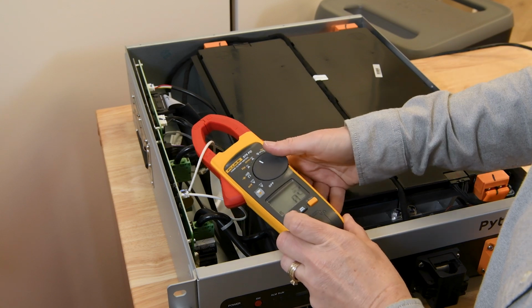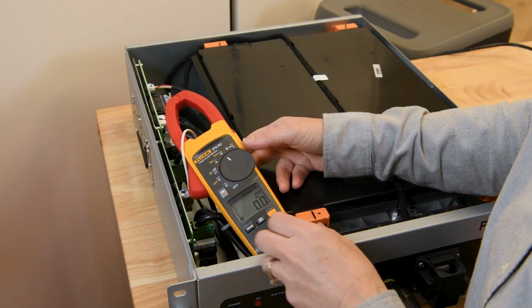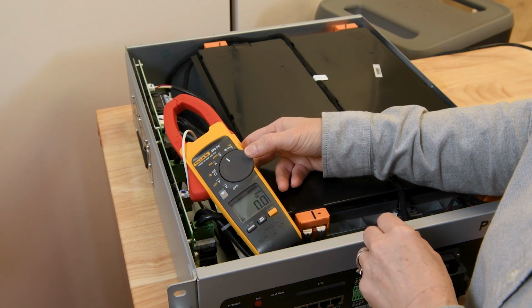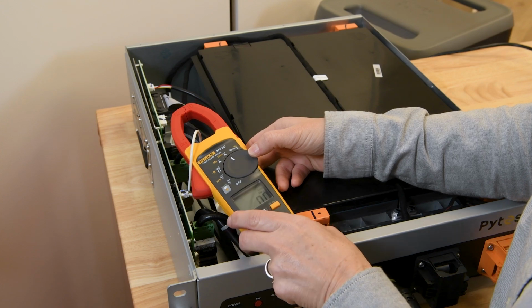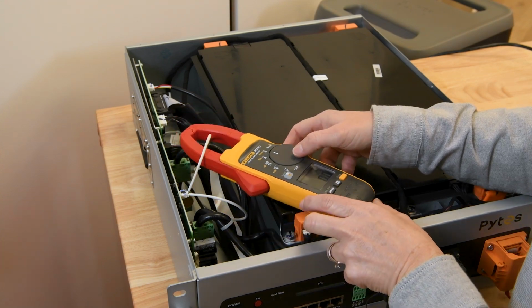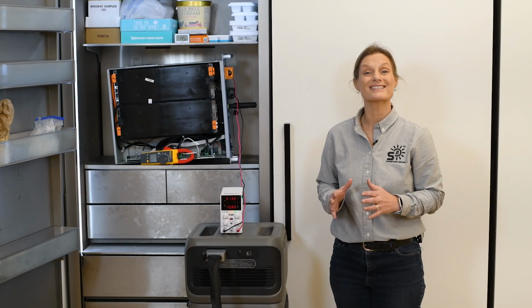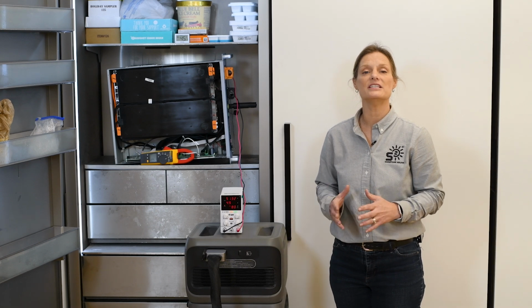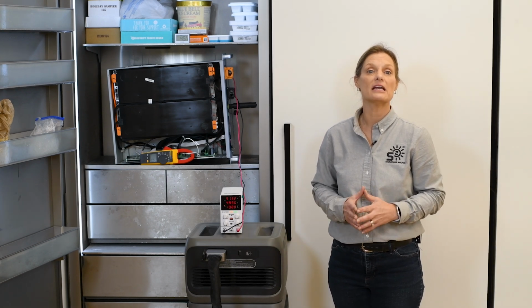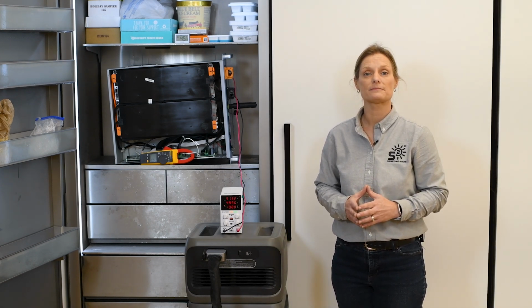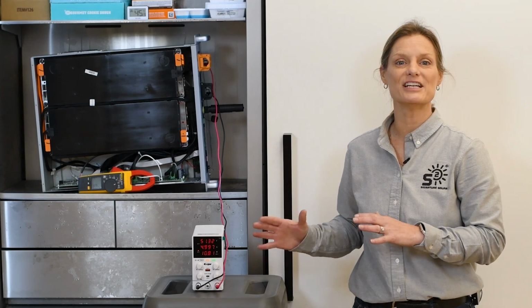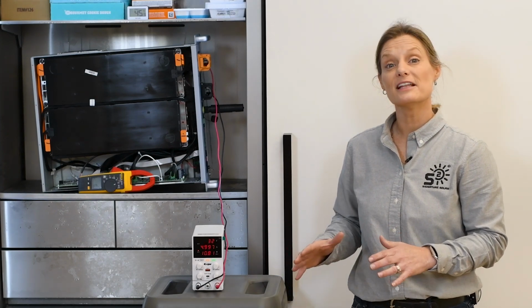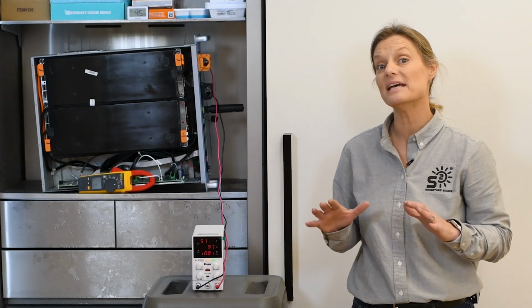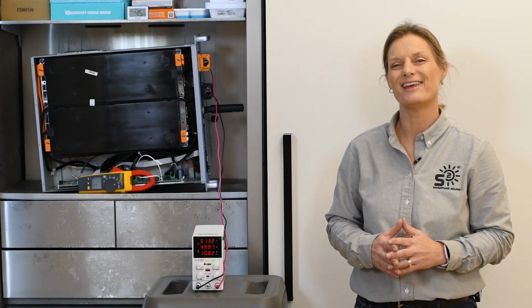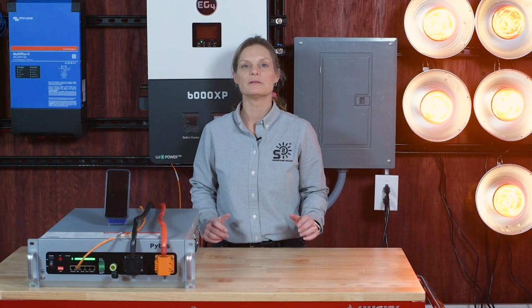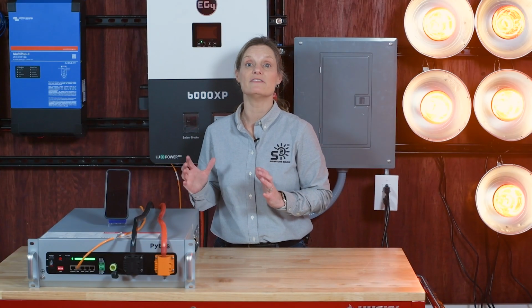As the temperature rises above 50 degrees Fahrenheit, we will see the heating pad turn off, as indicated by our clamp meter reading 0 amps. This automated heating feature is highly efficient, only engaging when necessary to maintain optimal battery temperature. For those installing batteries in extreme conditions, this level of smart control can make a big difference in performance and longevity. Let's review some of the standout features of the Pytes V5 battery.